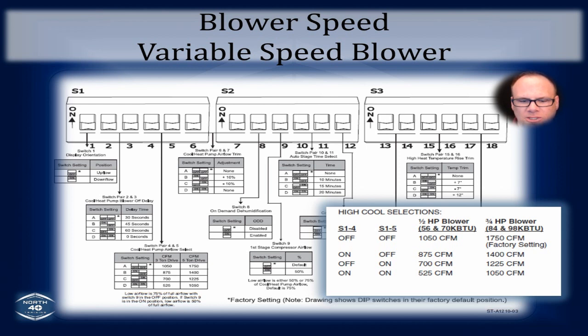These things are pre-programmed to achieve the CFM value that you set them at as long as you're less than 1 inch of static. So that control module that's on the end of that motor will maintain that 1050 CFMs on the off-off configuration for the half horsepower blower unless you go over 1 inch of static. Okay, so your measurement before the blower and after the blower has to be less than 1 inch of static in order to maintain that 1050. Now, once you get up above that 1 inch of static, it goes all over the place. You can't say that it goes down, it goes up. It's kind of a mixed bag. But one thing's for sure, the farther away that you can keep it from 1 inch of static, the better off you are.